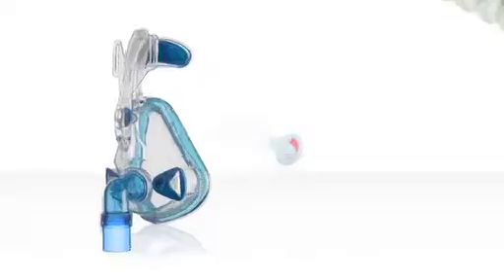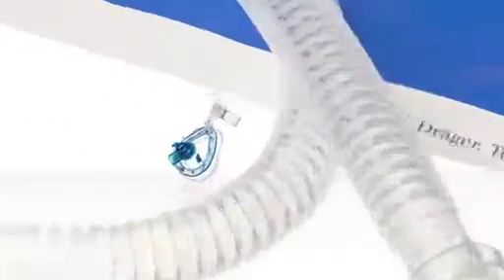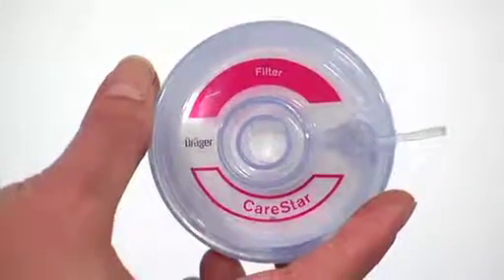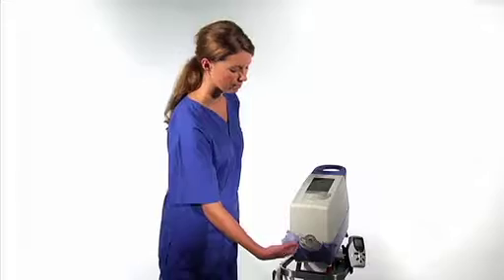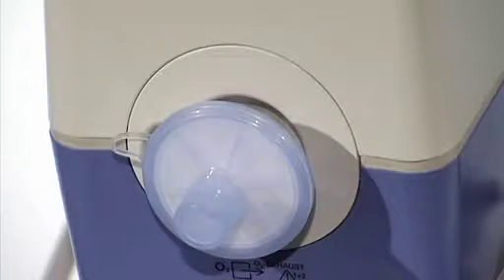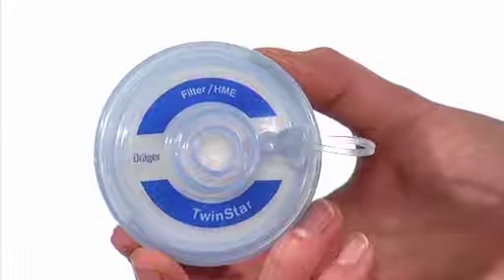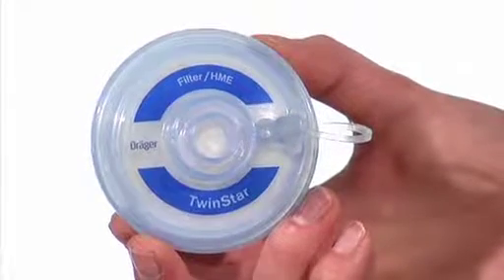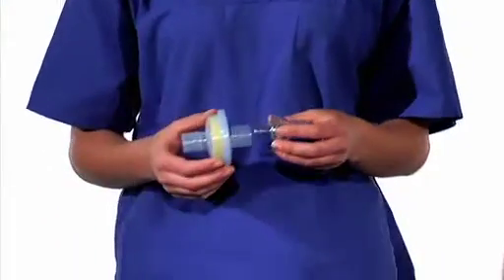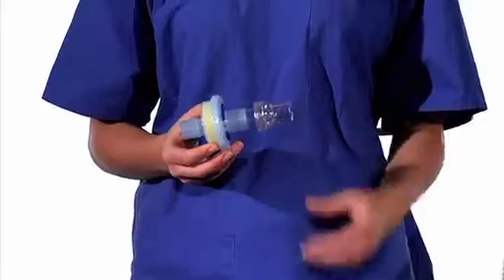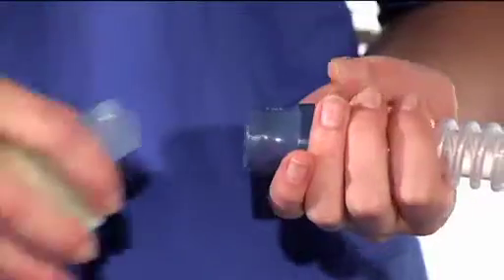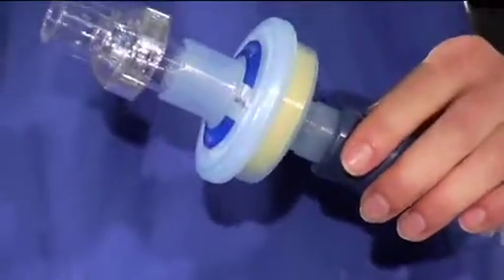To achieve optimal performance with Carina, it's recommended to use only the accessories listed in the instructions for use or the separate accessory list. To avoid cross-contamination, an inspiratory bacterial filter such as the CareStar 30 should always be used. Carina can also be used with an HME. Please bear in mind that an extra filter, or the use of filters with high resistance, could lead to higher breathing resistances. Please change the HME and the bacteria filter according to your hospital hygiene guidelines.